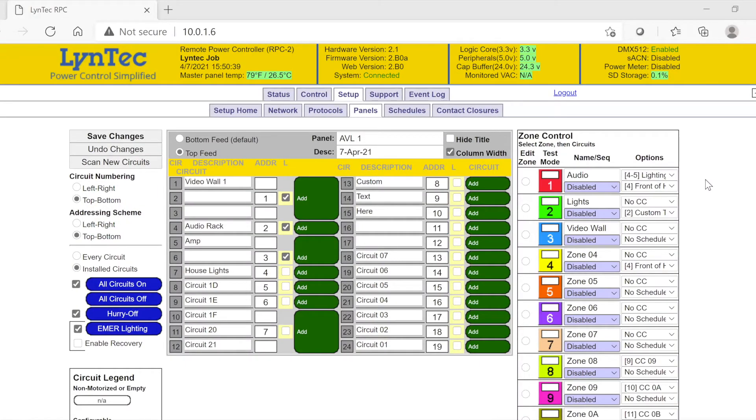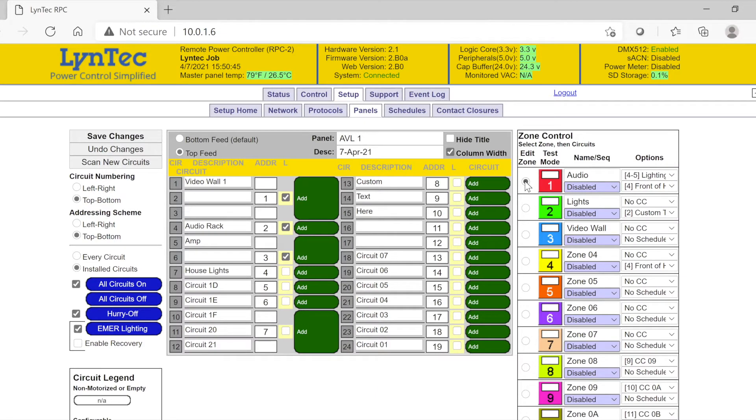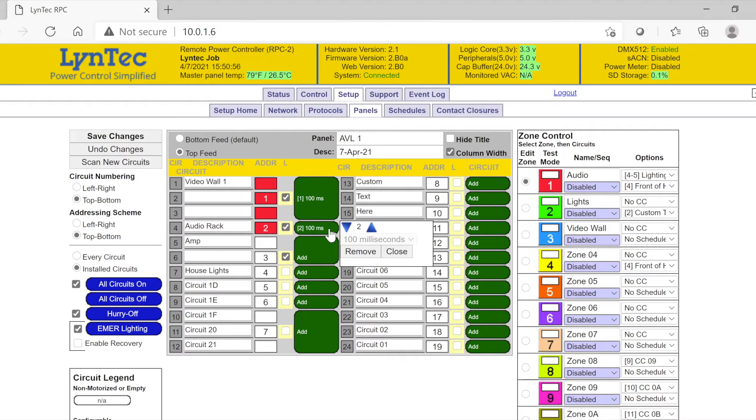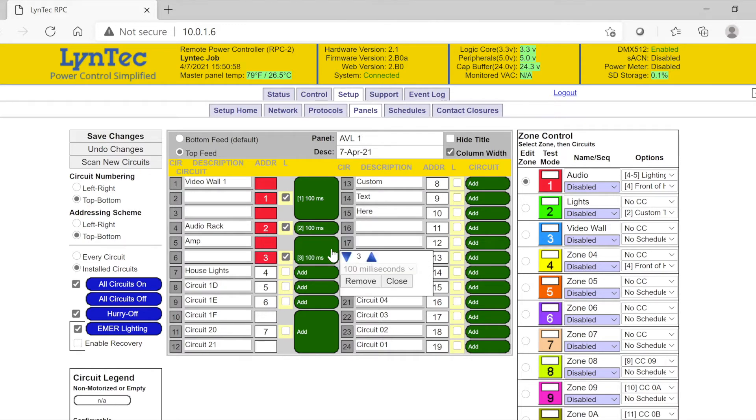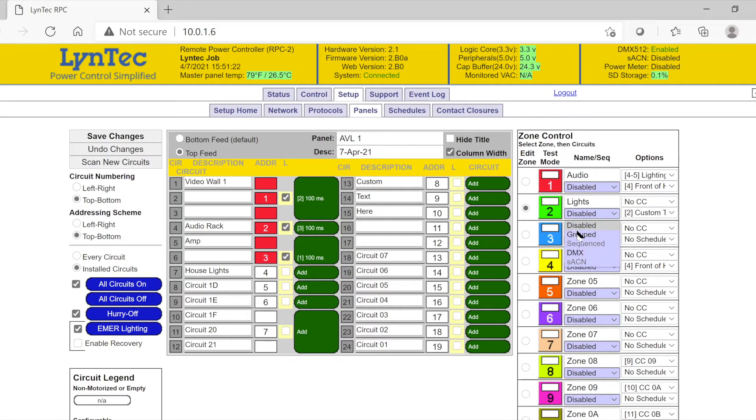Now that your zones have been created, we can move to the middle, or the circuit control section of the page, and begin to assign zone control to our individual circuits. First, make sure the radio button on the zone you are creating is still checked, and move your cursor to the first circuit to be designated. If you click on the green oval to the right of the address column, the oval should immediately populate with information, and you should see the corresponding address column turn the same color as the zone you are creating. The information in the green box should display the order in which that circuit will respond to the zone command.